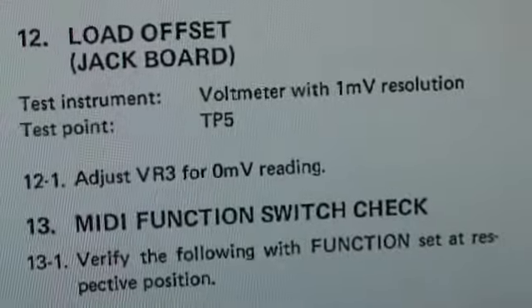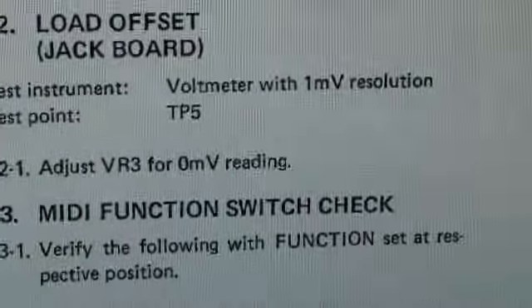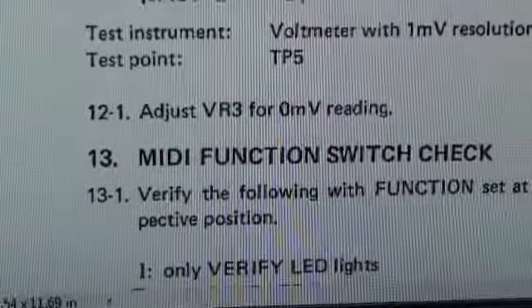Okay, load offset. Simple. There's one that anybody can do with a voltmeter. Test point is TP5 and you want VR3 adjusted for zero volts.